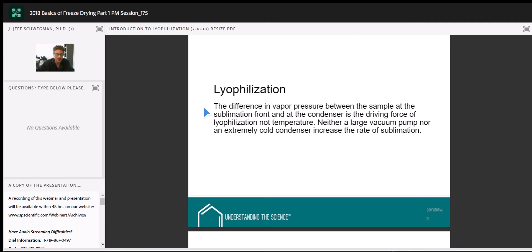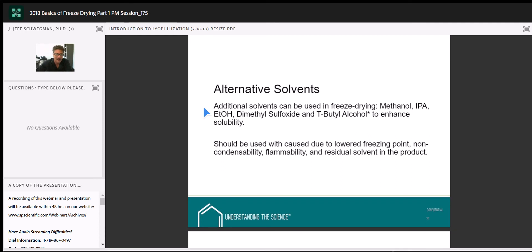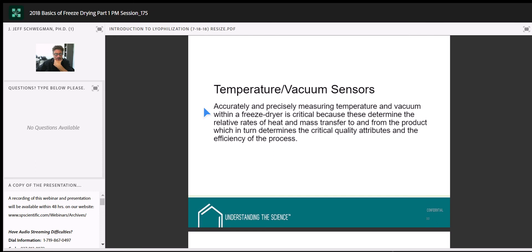For vacuum sensors, hopefully nobody is still using mercury manometers — though I have gone to companies where I've seen them. They're definitely old technology and have obvious issues with mercury. Mostly what we see today are thermal conductivity gauges — a special version called a Pirani gauge — coupled with a capacitance manometer. The capacitance manometer is the modern gauge most people use in freeze-drying.